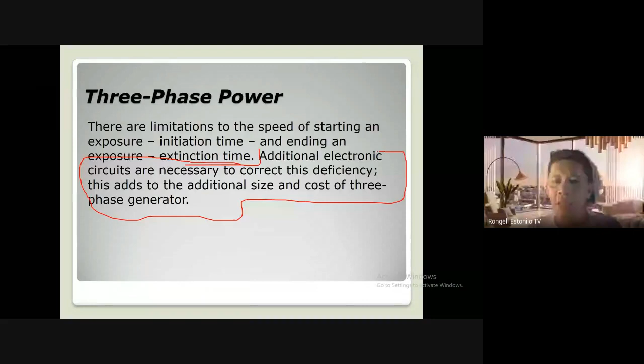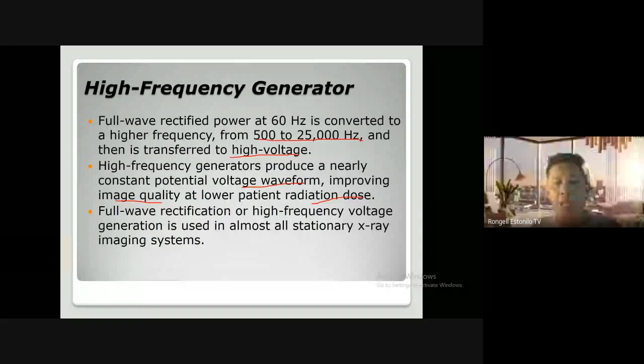So next we have the high frequency generator. Talaga maganda to. So full wave rectified power at 60 Hz is converted to higher frequency, from 500 to 25,000 Hz, and then is transferred to high voltage. So high frequency generators produce a nearly constant potential waveform, improving image quality at lower patient radiation dose. So full wave rectification or high frequency voltage generation is used in almost all stationary imaging systems. So one advantage of the high frequency generator is its size. So they are very much smaller than 60 Hz generators.